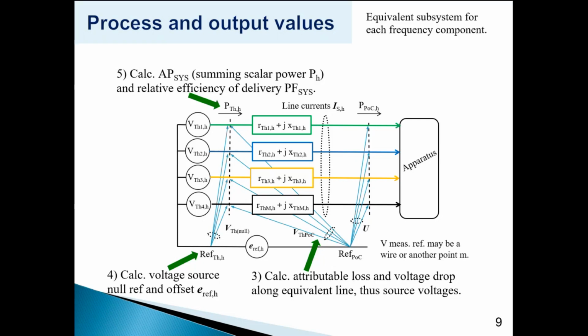Now remember I said, top right-hand corner, you have an equivalent subsystem for every frequency component. So this system for fundamental frequency is drawing power. But the fifth harmonic subsystem is exporting power from the same rectifier load. And because PPOC is defined as positive from left to right, the harmonic pollution power is flowing right to left, and we call that negative power, negative current. Does that help? Yes, thanks, Prof.